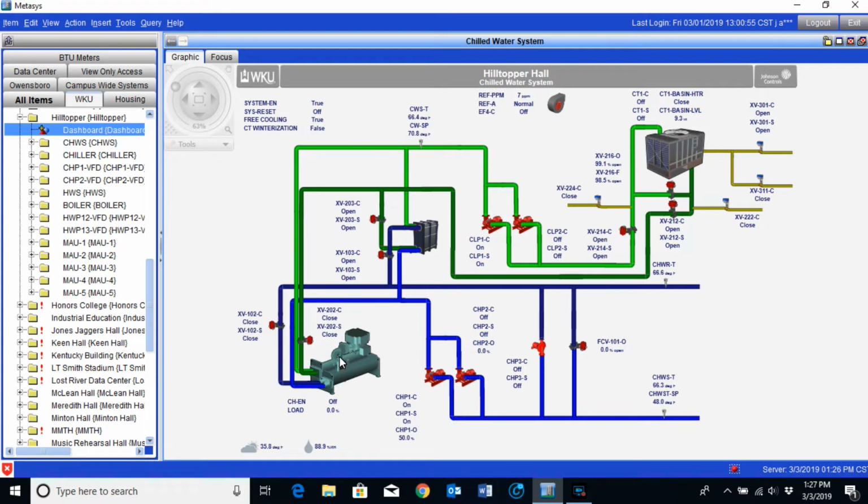I wanted to begin by showing you that you can see here, this is the chiller, if you can see where the mouse is pointing, and here is the plate frame. This is basically just a big heat exchanger. These two valves here are isolation valves on the heat exchanger, and we also have isolation valves on that chiller. So when the weather outside gets low enough that we cannot run the chiller, we will enable the plate frame system.